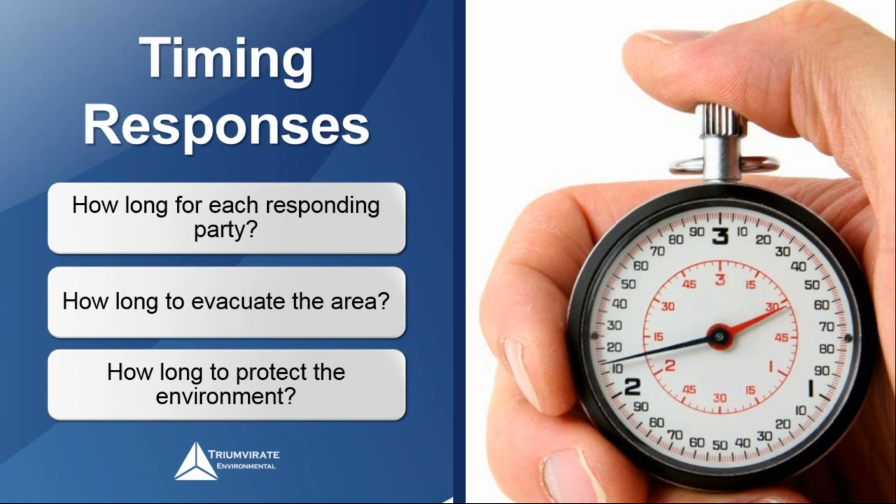The quickest one that we've seen in doing these types of spills is actually having a shutoff valve and being able to shut off how your tanks can discharge to the sewer. Now, if you can go in and shut this down, you just want to make sure that you're not going to back up into your facility and create another problem. That is something you need to take into account at the time of response, and if you have additional storage on site.